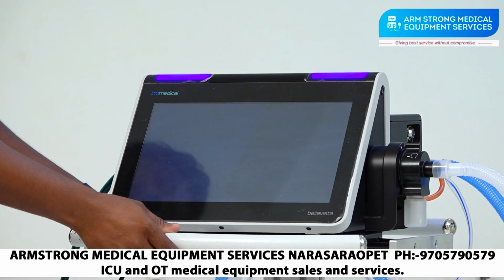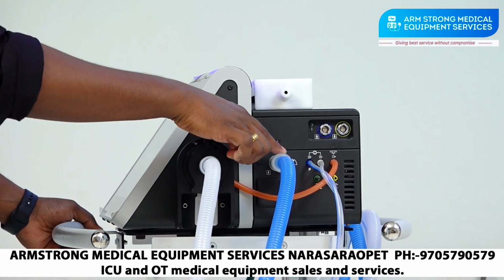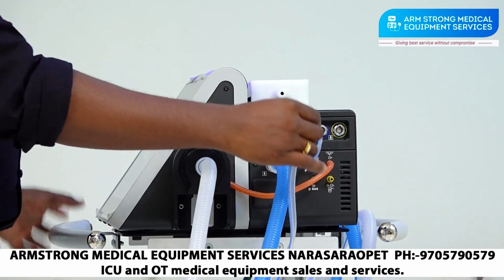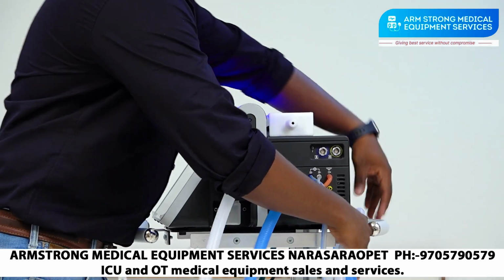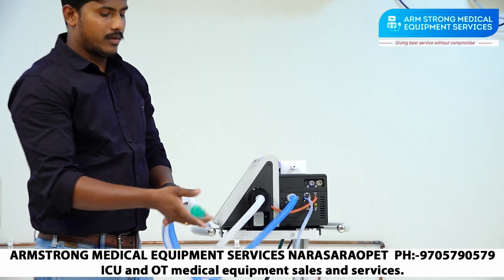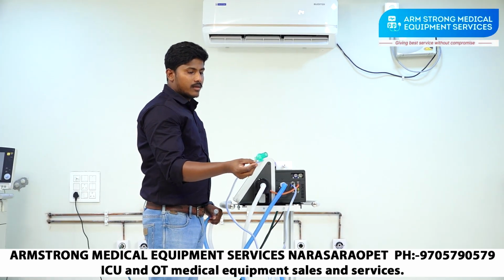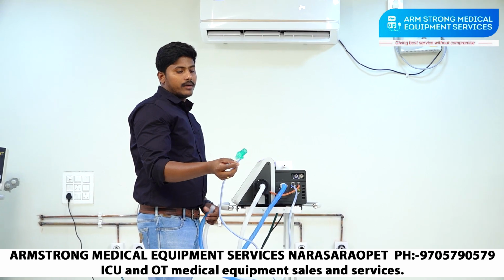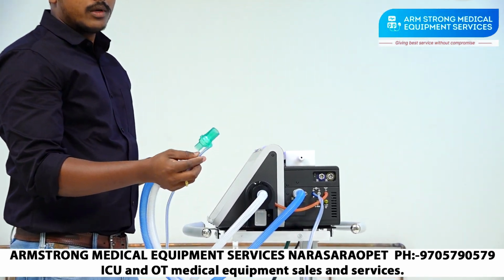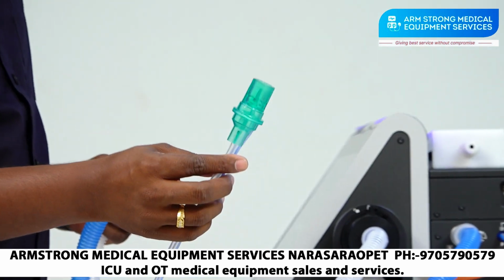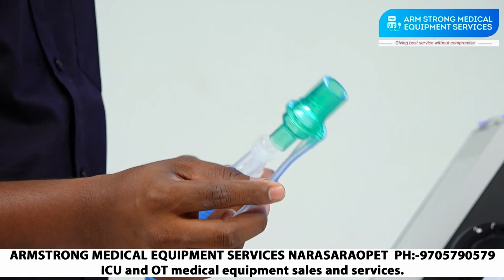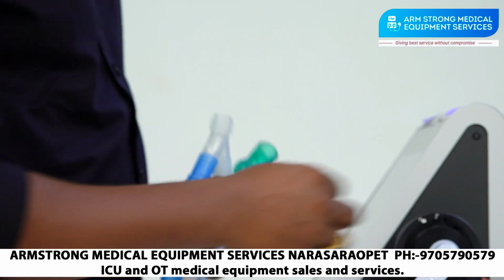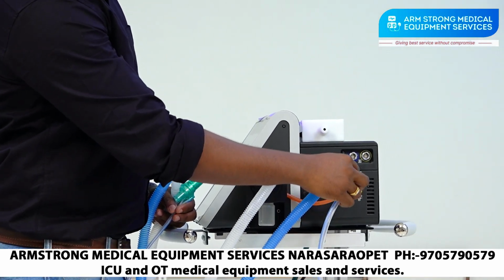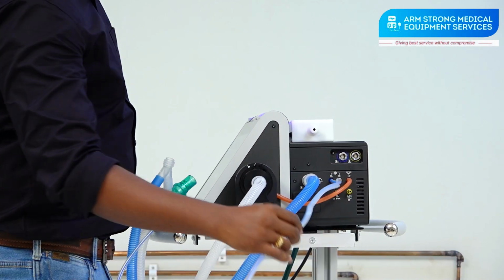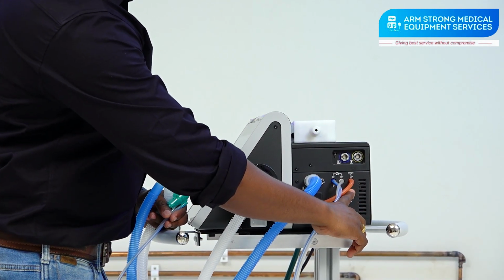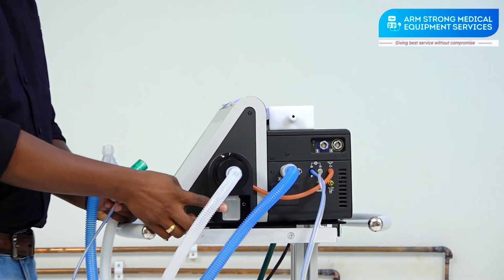While it is booting, I will explain these parts also. This is the inspiratory and this is the expiratory, and these are small tubings. This is the differential flow sensor. We connect this one between the Y-piece and the patient ET tube. It is very useful to show accurate results for the tidal volume and respiration rate. Here you see, positive and negative are both connected. This is the differential flow sensor. And here you see, this is the nebulization, and this is the exhalation valve and water trap.